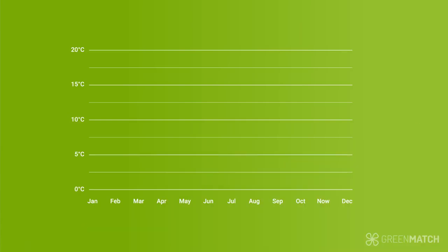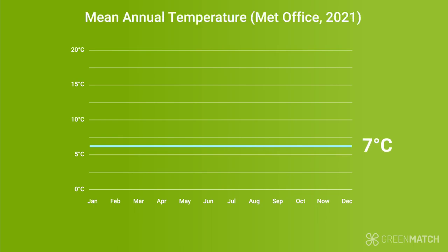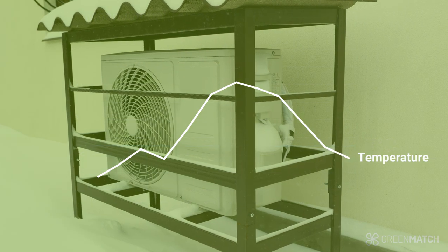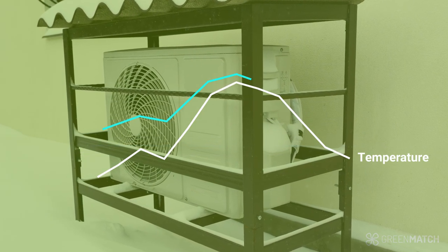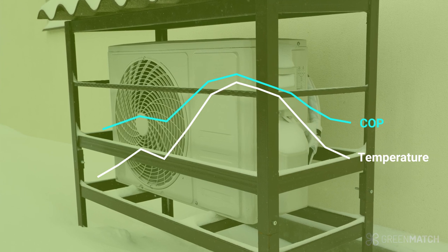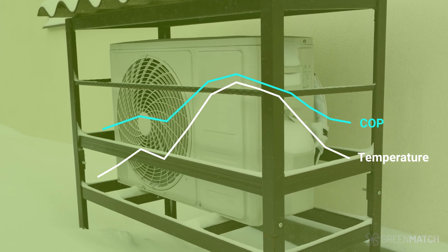Most air source heat pumps will run efficiently at temperatures as low as 7 degrees C. But Met Office data has previously shown that the average UK temperature from November to March is consistently below 7 degrees. In these winter months, it is likely that a heat pump's coefficient of performance would be slightly lower, depending on how cold it gets.